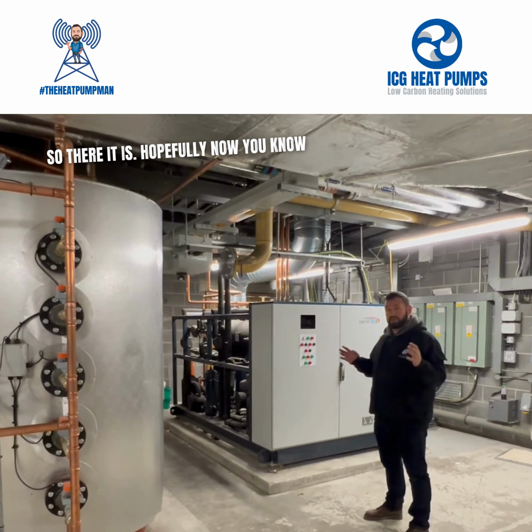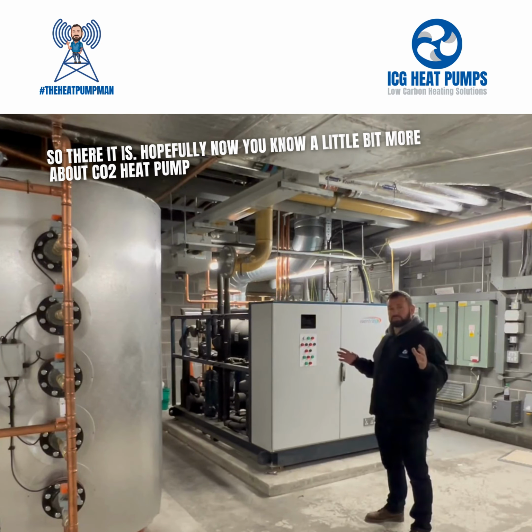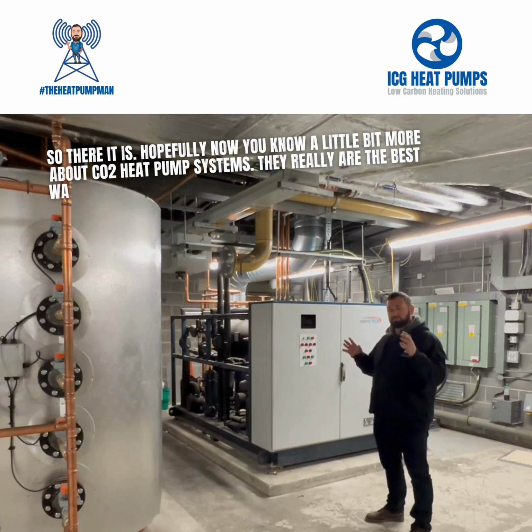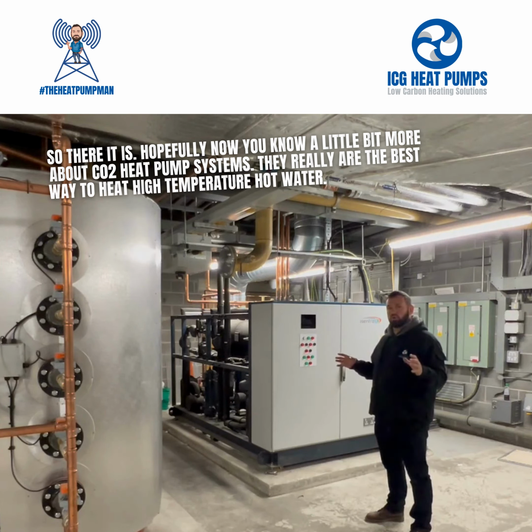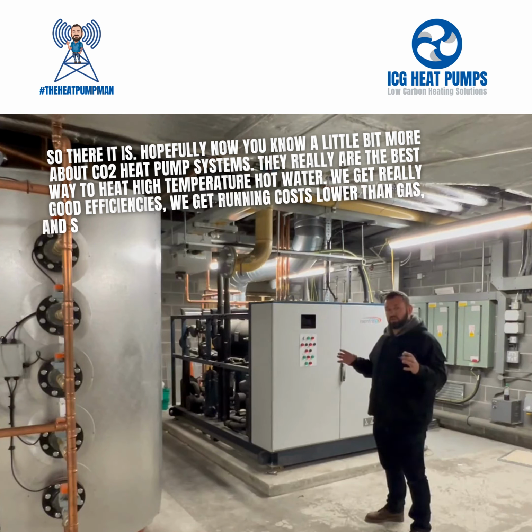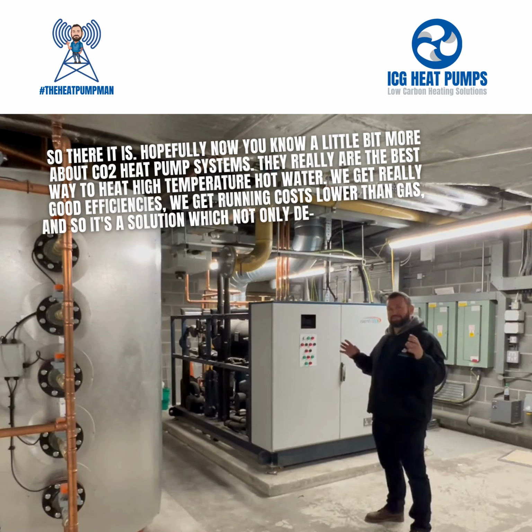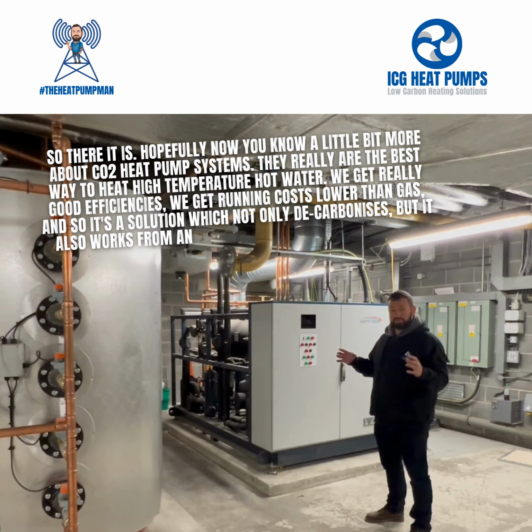Hopefully now you know a little bit more about CO2 heat pump systems. They really are the best way to heat high temperature hot water. We get really good efficiencies, we can have running costs lower than gas, and so it's a solution which not only decarbonises, it actually works from an economical point of view as well.